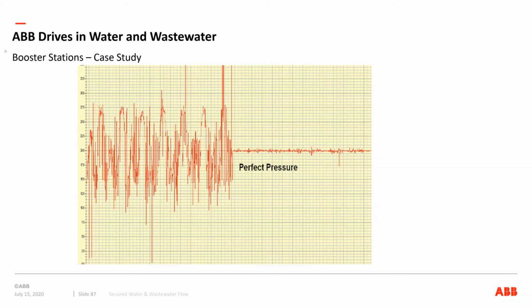But future trends we're seeing, again, energy savings, predictive maintenance. If the motor's starting to run hot, why is it running hot? Is it running hot because of the bearings? Is the shaft out of line the way it's connected to the pump? Are the pump bearings failing because it's out of line? Is it getting different shock loads? Are we getting debris and solids coming through there? There's lots of things. There's lots of data here. One of the challenges that a lot of facilities have is the amount of data that they're receiving.